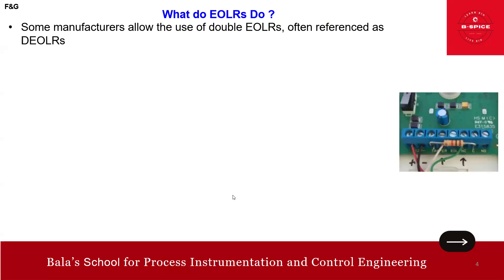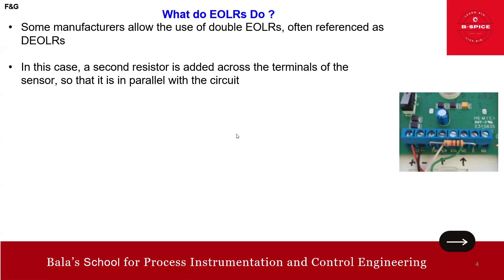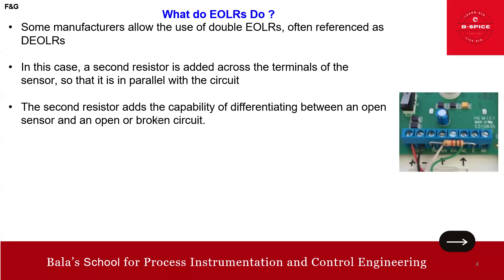Some manufacturers allow the use of double EOLR, known as DEOLRS — double end-of-line resistors. In this design, a second resistor is added across the terminal in addition to the cable end resistor. It is terminated across the terminal of the sensor so that it is in parallel with the circuit.